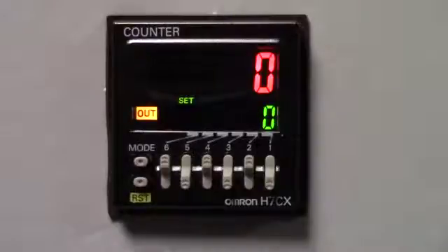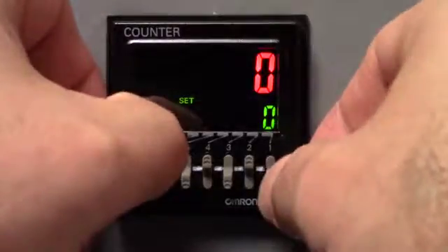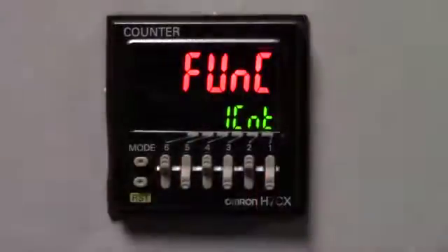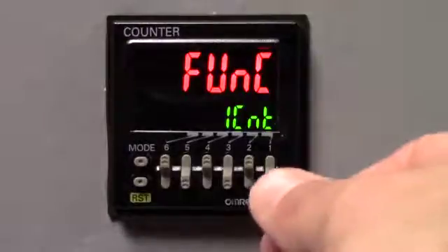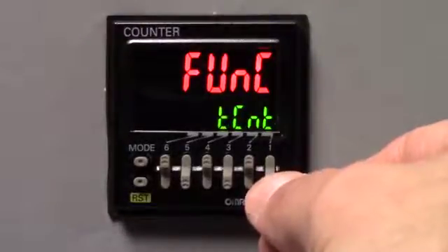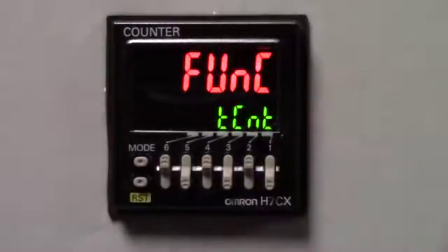That being said, we need to get into the parameter setup, and by doing that, we're going to press the mode key first, and then the number one key. So, that takes us into the parameter setup. You have a one-stage preset, which is the factory default, which we are not going to do. We are actually going to do a total and preset counter. So, we're going to take the number one key, and we're going to toggle it until you have the T-CNT.